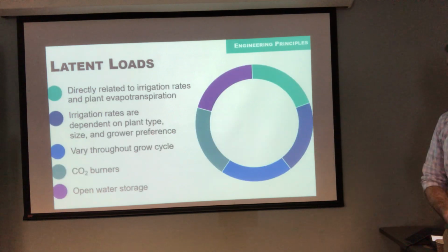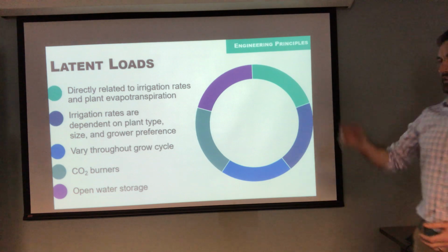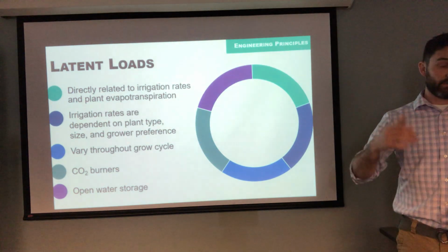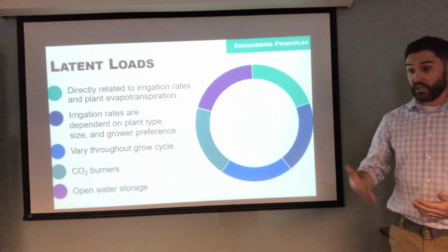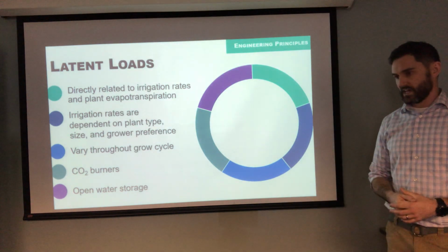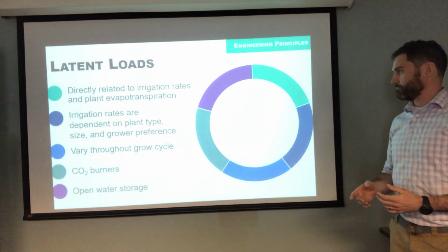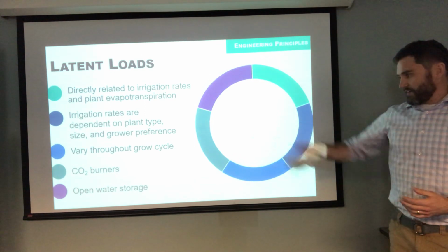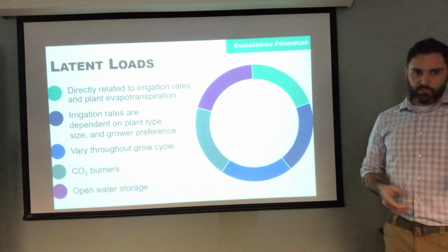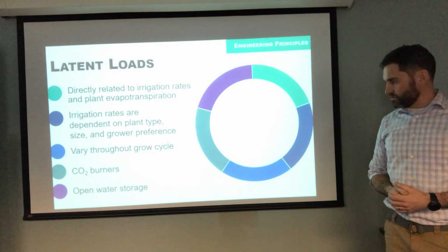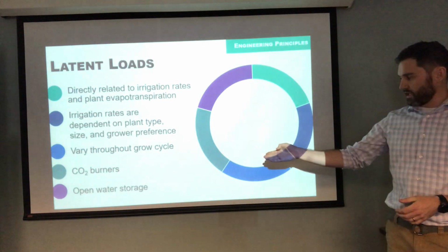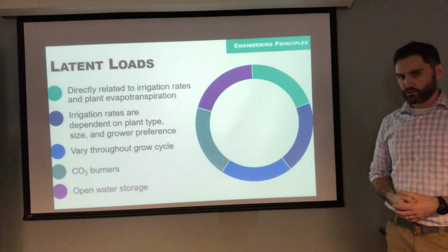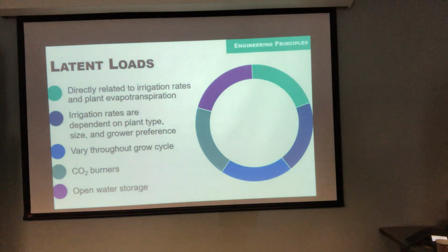What are the sources of your latent loads? It's directly related to irrigation rates, the amount of moisture, the bulk liquid water you're putting into your veg and flower rooms — that's the primary source. If you have a CO2 burner, you can get a tiny bit of additional moisture, hardly worth mentioning. And depending on your methods, if you have open water storage, you can get evaporation off of that water as well.